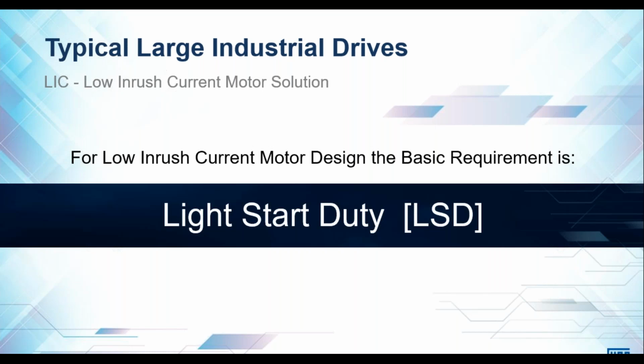It can be used in light starting duty applications only, because if we need a high locked rotor torque, it is difficult to get a high torque during startup and get a low starting current. You'll see that those two parameters are inextricably linked.